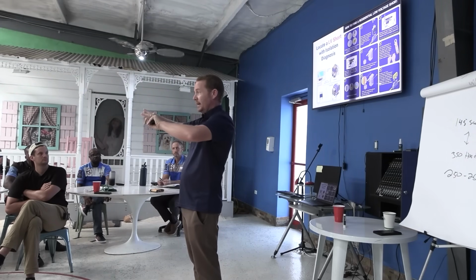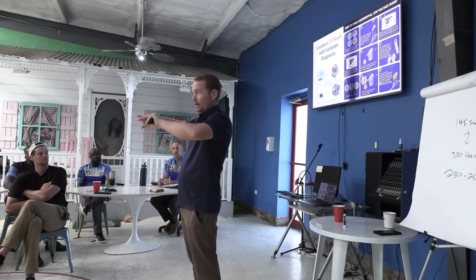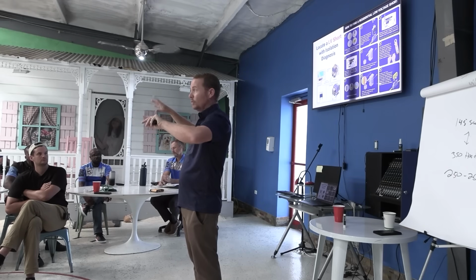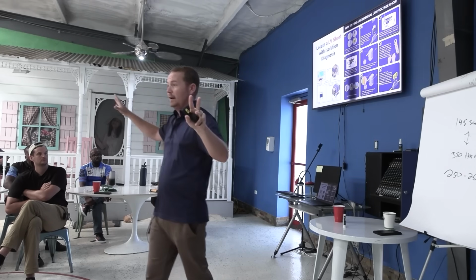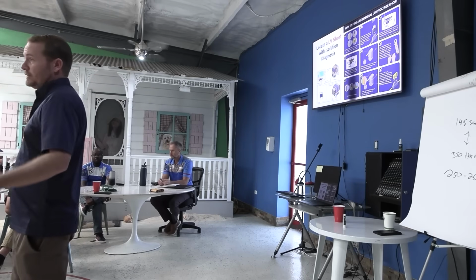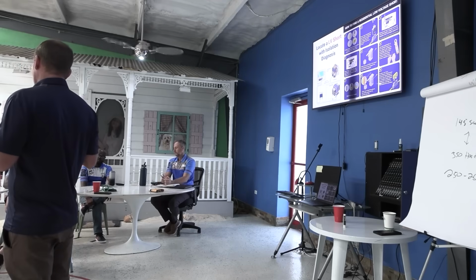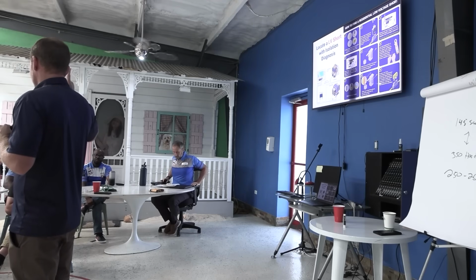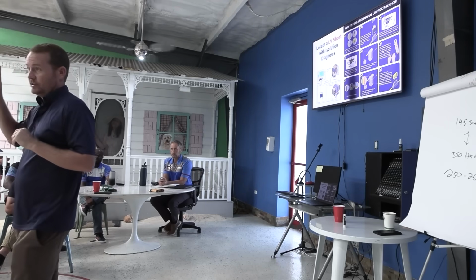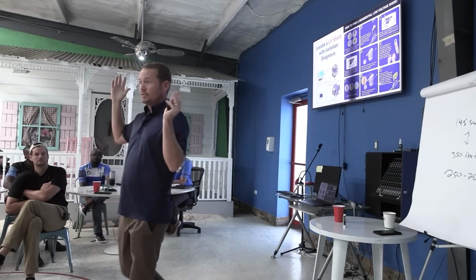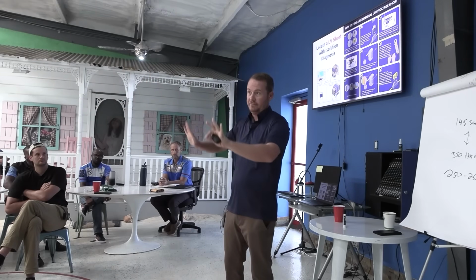So I'll start by energizing fan on. Does it blow? Does the blower come on? Blower comes on. Which circuit's okay now? G. I know G's okay now, right? So now I actually know a couple circuits are okay, I know R is okay, it's not shorted, and I know G is okay, it's not shorted. If I put the fuse in and it blows right away, okay, it's R, if I had it off and isolated.